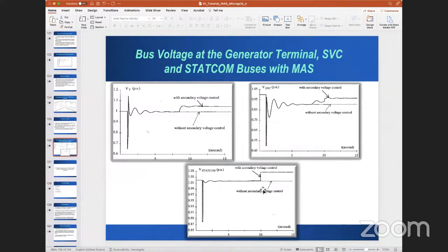AVR here, and STATCOM control here. Again, the STATCOM is not doing anything at its location because its voltage is within limits. But it can add a little bit more and still stay within limits, still below 1.05 — we can't quite see it, but most likely it's at 1.05. So it's within limits, and we can help this bus keep the voltage within limits.